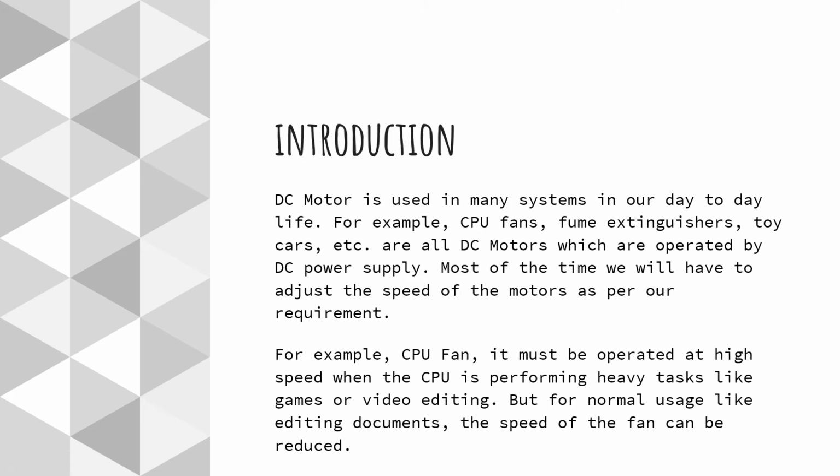A more efficient way to proceed is by using the pulse width modulation technique to control the speed of our DC motor. The major reason for using pulse width modulation in DC motor control is to avoid the excessive heat dissipation in linear power amplifiers. The heat dissipation problem often results in large heat sinks and sometimes forced cooling. PWM amplifiers greatly reduce this problem because of their much higher power conversion efficiency. Moreover, the input signal to the PWM driver may be directly derived from any digital system without the need of a DA converter.